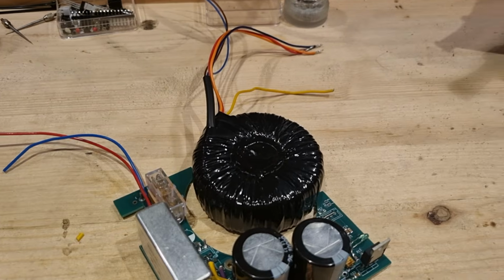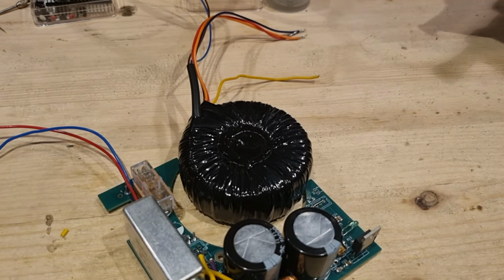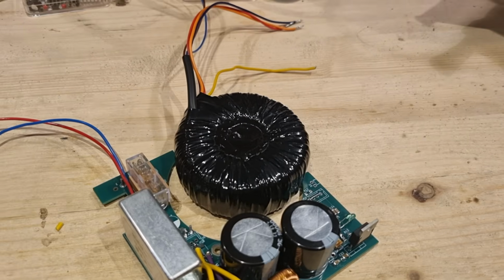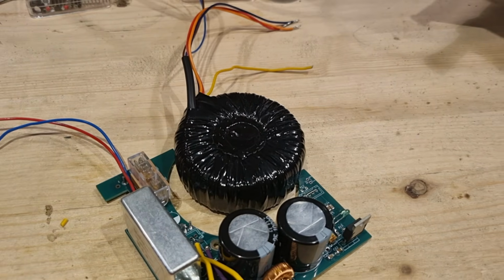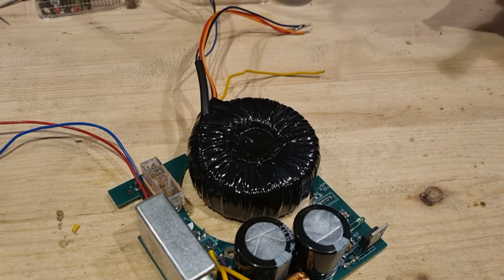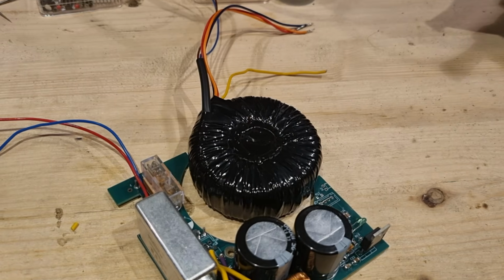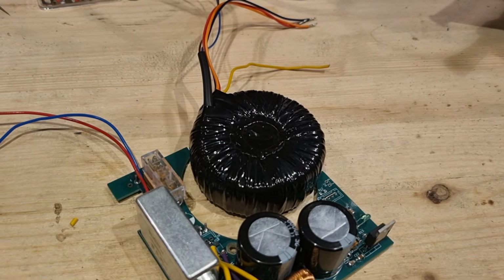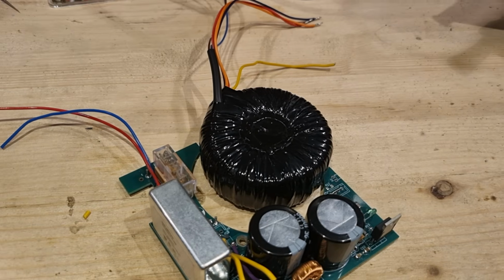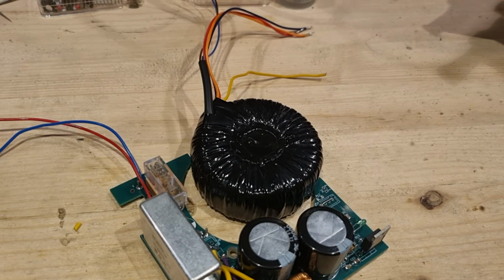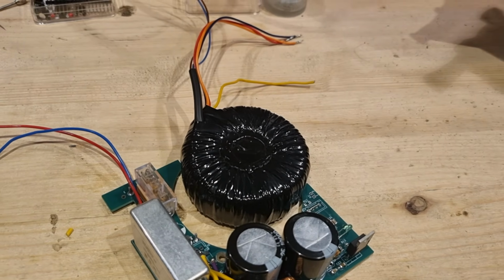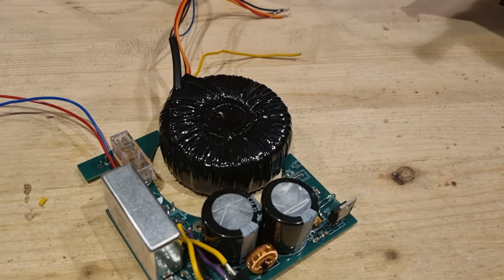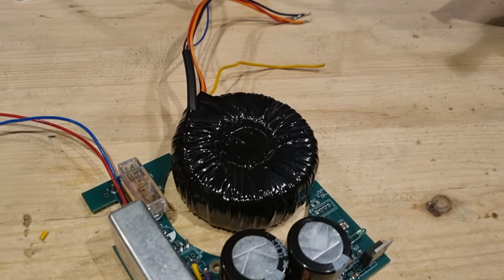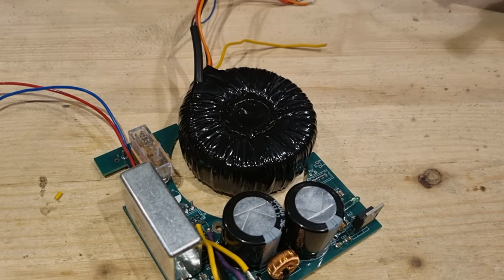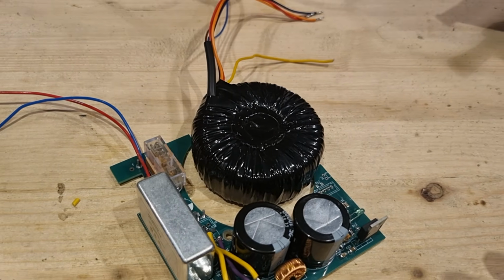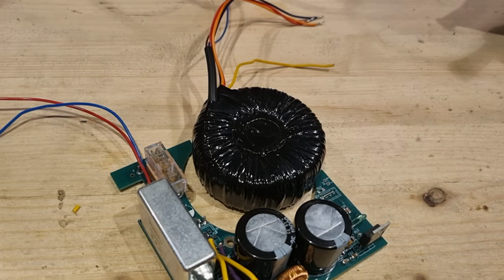Secondly, these have also been designed to be low mechanical noise, in a couple of ways. First, I use an over-specified toroid, an iron core considerably larger than it needs to be for the power I'm outputting. Second, that toroid is submerged inside varnish, completely potting the entire innards of the toroidal core, which prevents the iron within from vibrating. So this transformer is also almost 0 mechanical noise.